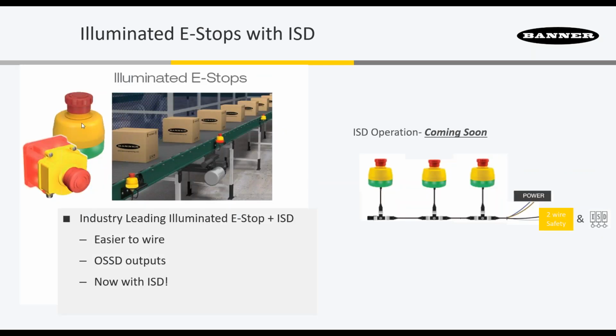And as we integrate this into our Illuminated E-Stops, when we talk about the 3 or 4 wire system, it's actually a 2-wire system for the safety portion of the E-Stop, because again, we're using OSSDs now on our E-Stop. So in this setup, we'd have E-Stops with a T connector, 4-pin cables, power goes to 2 pins, and safety to the other, OSSDs and ISD are on the other 2 wires. When you press one of the E-Stops, the E-Stop that is pressed will flash red, and the other ones will remain in whatever state they were in before. So you can visually, locally identify what e-stop was pressed. But then on the HMI and via other alerts, you could send out information to someone to also point out that it's this second e-stop.